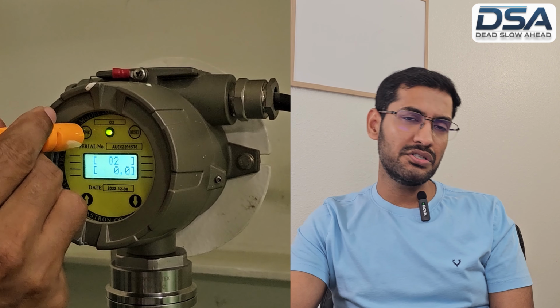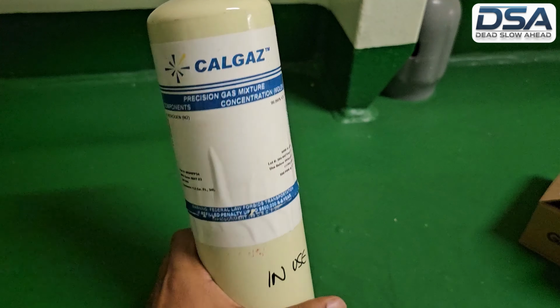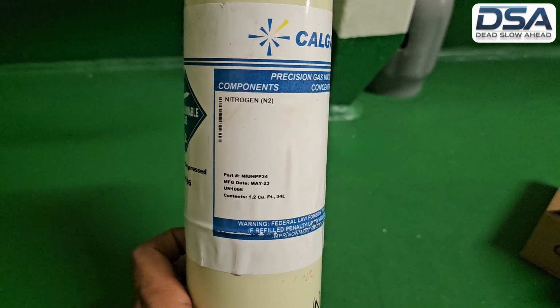Now we move to the calibration procedure. For calibration we do two different procedures: zero calibration and span calibration. Zero calibration means we provide an environment equivalent to zero oxygen percentage. In our case we use a 99.9% nitrogen gas mixture, which provides a 0% oxygen atmosphere. For span calibration, we use normal atmospheric condition, because we have to provide the full range, the full span of atmosphere. So we let the sensor run in the normal atmosphere. It should ideally show 20.9 percent, and in the previous case it should show around 0 percent.